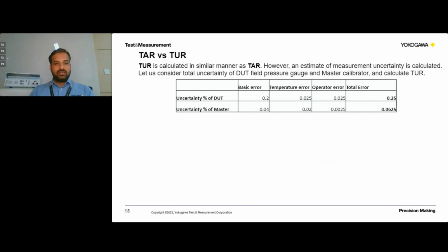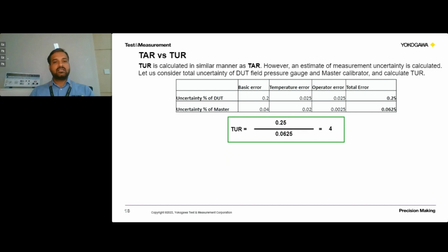If you see, for any of the DUT or any of the master, basic accuracy or basic error will be defined. Then we need to consider the deviation or the error due to, for example, temperature change. So that error will be added, and error which may arise because of operator or because of manual intervention, we can say. So that accuracy also we need to consider, and then we will consider total uncertainty of the DUT and total uncertainty of the master. So ratio of these two will give us test uncertainty ratio.